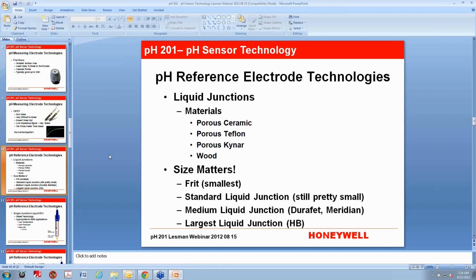And then the largest liquid junction would be similar to something on what we call our HB sensors. And that liquid junction starts at the outside of the glass measuring electrode and goes all the way to the inside of the body of the sensor. So it is the largest liquid junction. In most processes, I like that very large liquid junction because there's less chance of coating and plugging up the sensor. Okay.